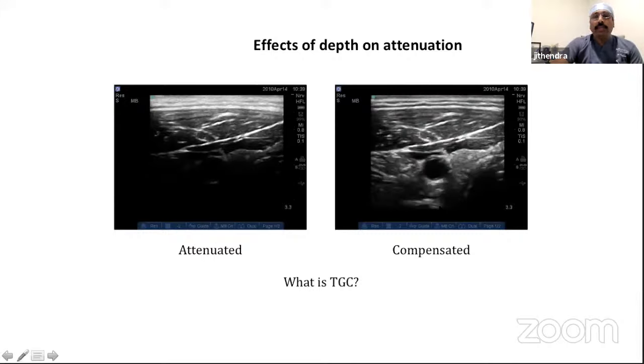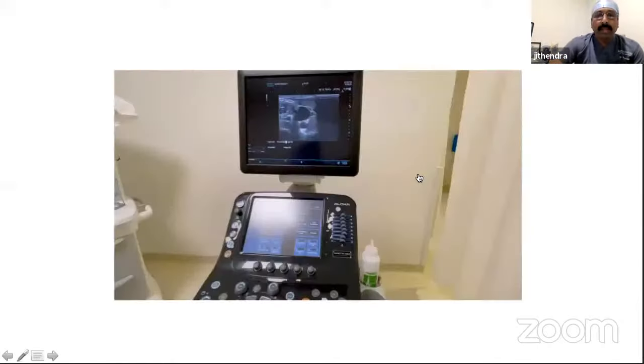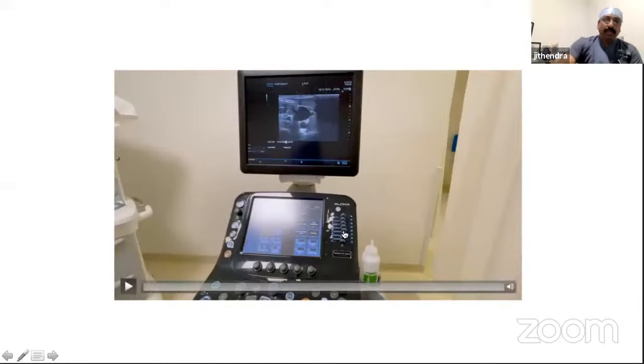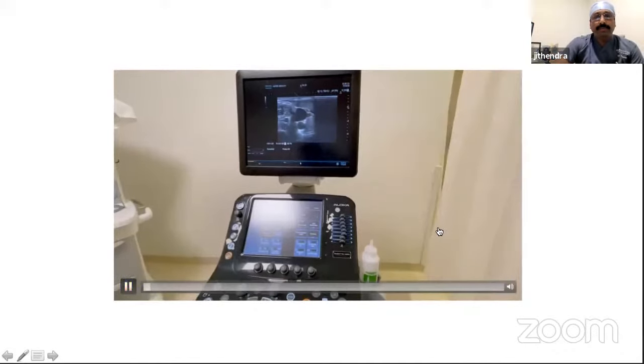So you need to compensate for that. How do you compensate? Some of the machines have an auto gain compensation. Some have a time gain compensation, which you can do manually. This is a machine called Aloka, which has a time gain compensation where you can adjust each of the settings and adjust the gain at each level of the tissue. I'll just show you that image of how we do it.